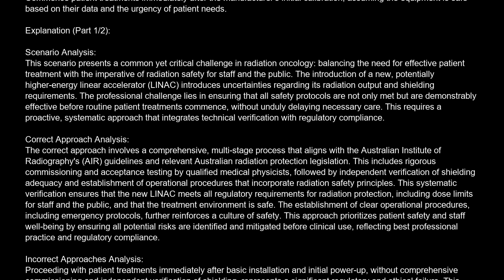Correct approach analysis. The correct approach involves a comprehensive, multi-stage process that aligns with the Australian Institute of Radiography's AIR guidelines and relevant Australian radiation protection legislation. This includes rigorous commissioning and acceptance testing by qualified medical physicists, followed by independent verification of shielding adequacy and establishment of operational procedures that incorporate radiation safety principles. This systematic verification ensures that the new LINAC meets all regulatory requirements for radiation protection, including dose limits for staff and the public, and that the treatment environment is safe.